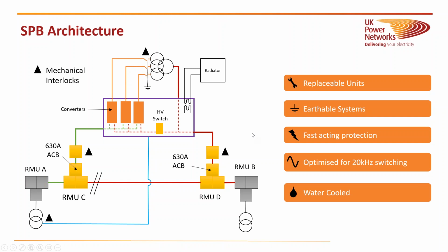Safety is our number one priority in UKPN, and we've had to set it up in a way that it has lots of protection, and that we're complying with the distribution safety rules. All of this system is considered an 11 kV system. Even the converters, which actually operate at 1,000 volts, the whole thing is 11 kV. So we've had to make sure that it can be earthed at all points. The RMUs are earth switches, and then we've had to add these earth switches next to this isolating transformer so that when there's maintenance, we're able to earth it.